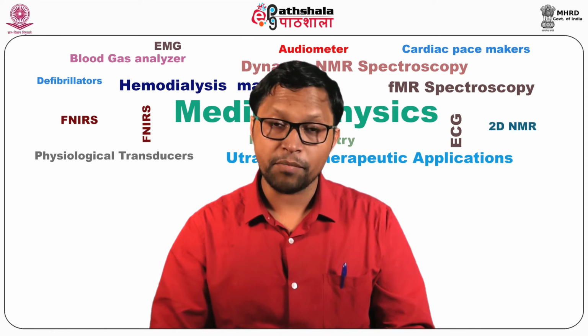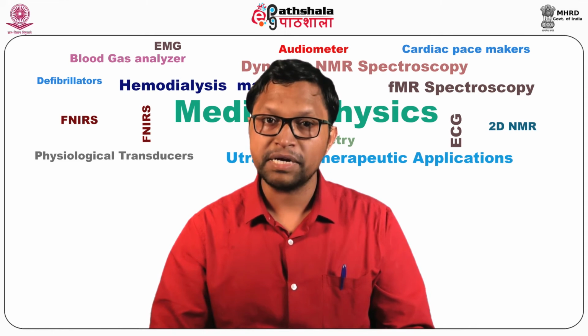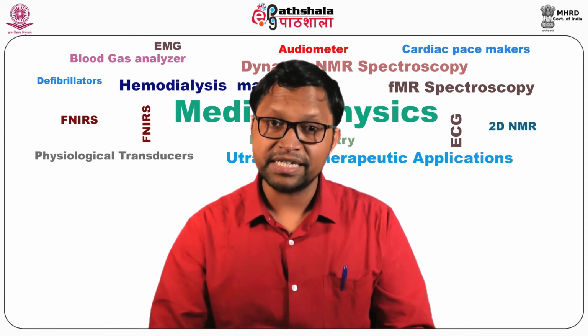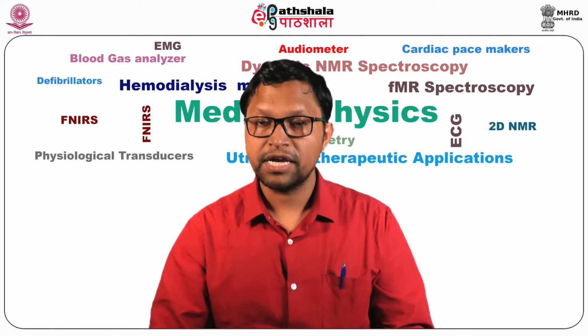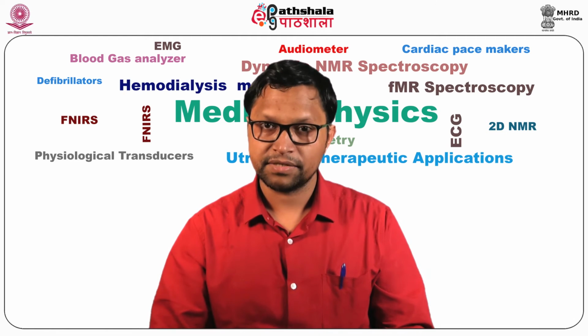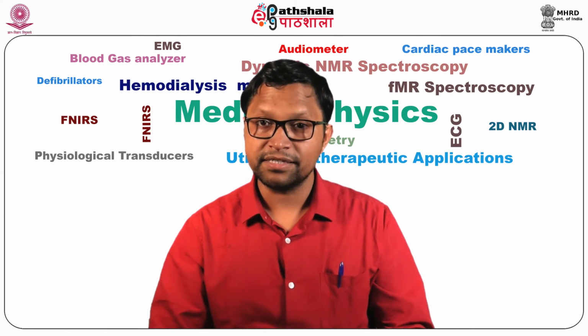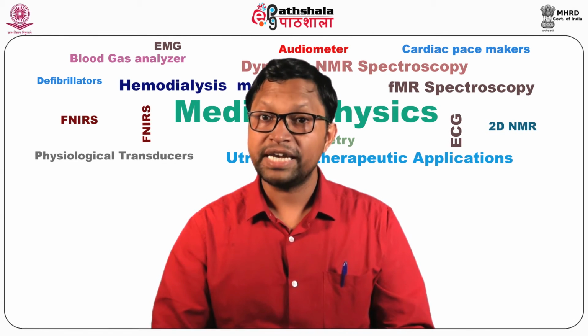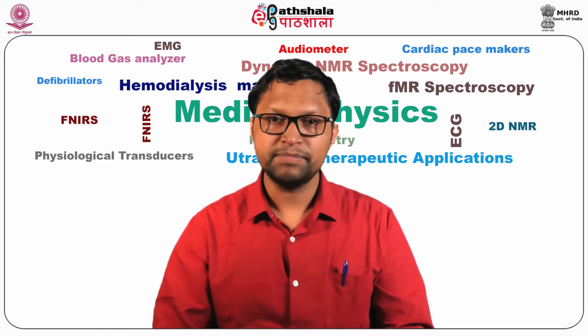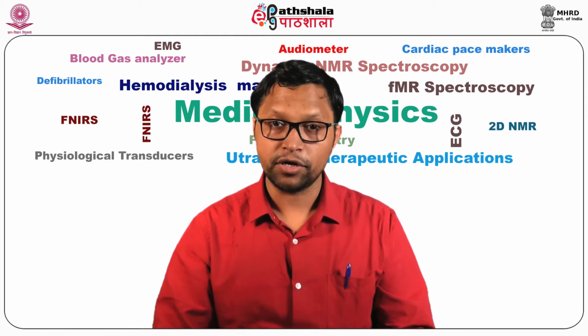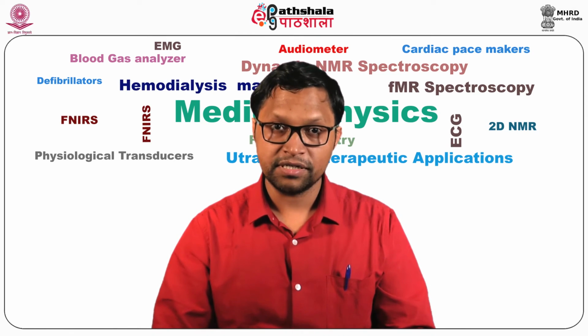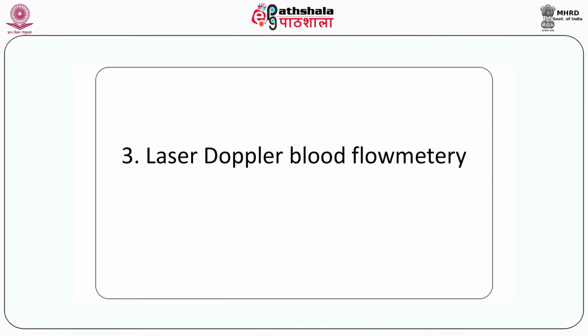The beam from a low power laser from a laser diode penetrates the skin sufficiently to be scattered with the Doppler shift by red blood cells. The returning laser is captured by a laser detector. This method is called laser Doppler velocimetry or laser Doppler anemometry. This shows typical setup for laser Doppler flowmetry.